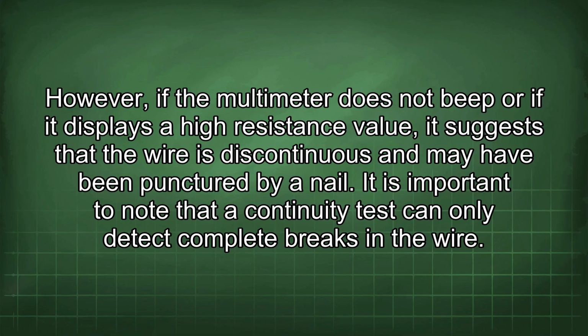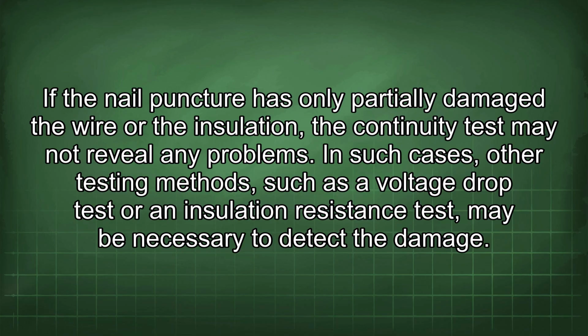It is important to note that a continuity test can only detect complete breaks in the wire. If the nail puncture has only partially damaged the wire or the insulation, the continuity test may not reveal any problems. In such cases, other testing methods, such as a voltage drop test or an insulation resistance test, may be necessary to detect the damage.